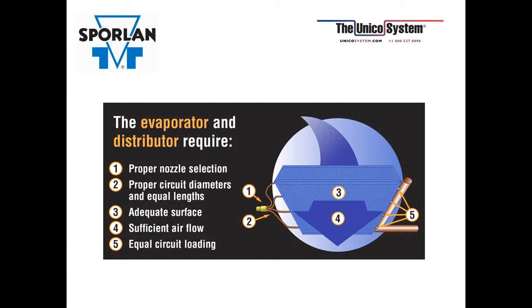And then in point 5, if you suspect that the unit is hunting, an easy check is to take a temperature reading at each of the outlets at the header. They should all be the same temperature. If you see one that's higher, then you probably have a problem with the distribution, so you might want to go back to number 1 and number 2 a little more thoroughly, because they might be blocked.